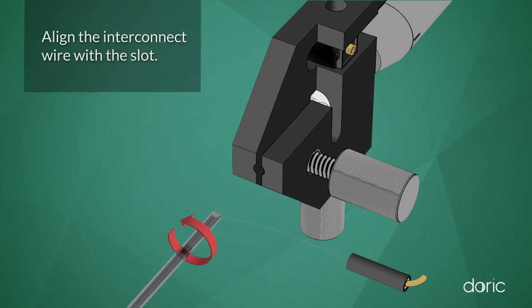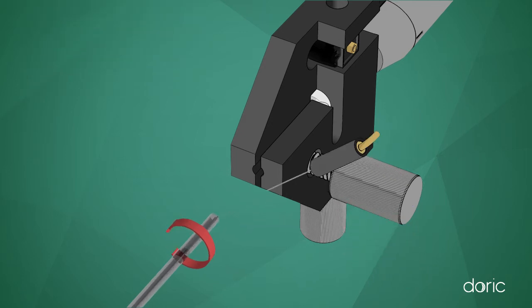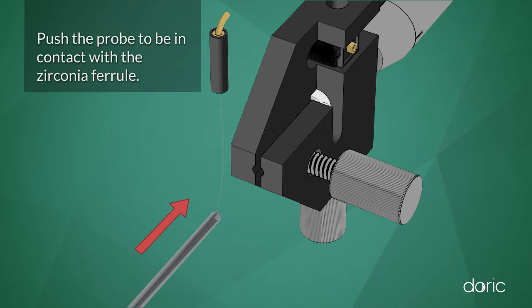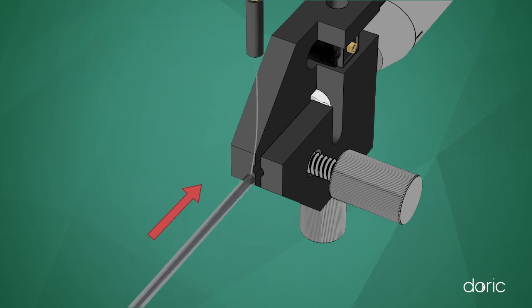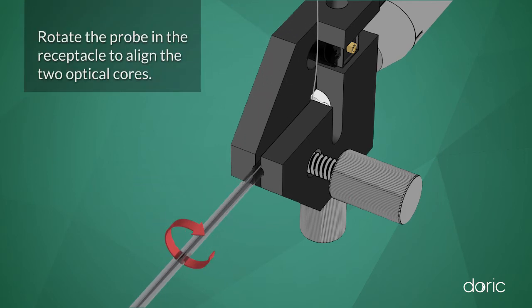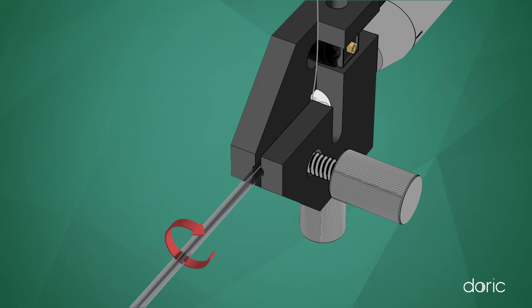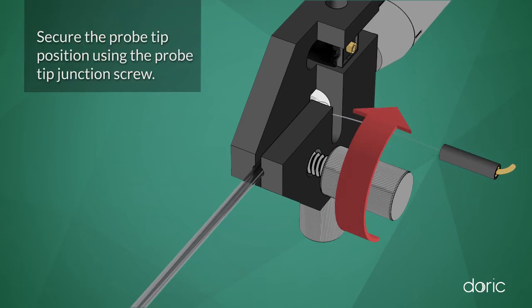Align the interconnect wire with the slot. Push the probe to be in contact with the zirconia ferrule. Rotate the probe in the receptacle to align the two optical cores. Secure the probe tip position using the probe tip junction screw.